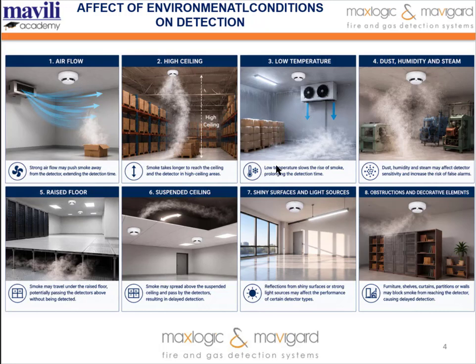You can see from here, airflow can delay the arrival of the smoke to the detector. In high ceiling spaces, the ceiling height can affect the time it takes for smoke to reach the detector. Low temperatures can affect smoke movement and also device selection, so the detector should not be affected by the cold air. Dust, humidity and steam can increase the risk of false alarms.